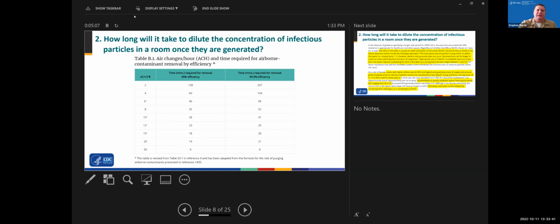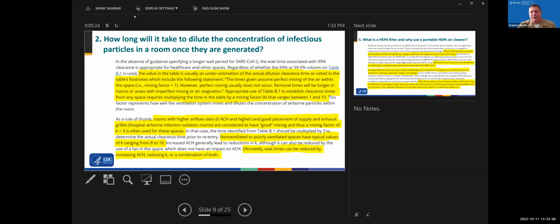But one thing I need to caution you on is that the table comes with a footnote that everybody forgets. The values in the table assume perfect mixing, and perfect mixing very rarely happens. So you need to multiply the times in those tables by a mixing factor. And a mixing factor is very difficult to determine. It takes very specialized equipment and some experimental trial and error to get that number. So you usually just apply a safe rule of thumb.